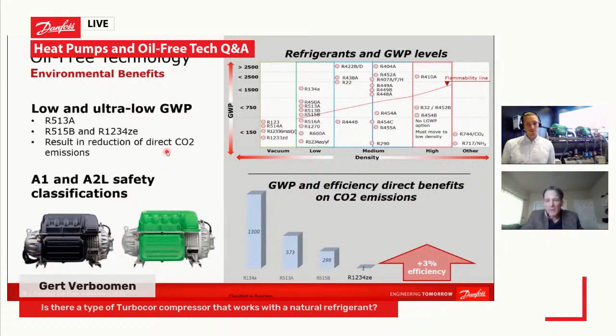One of the main related factors to this technology, as well as other turbo compressor technology becoming more prevalent in the market, is refrigerants and the push down to lower GWP levels. If you're going to push down to lower GWP levels and at the same time minimize flammability, that pushes you to lower density refrigerants. Lower density, or larger molecule, refrigerants in turn push you toward technology optimized to remove a high volume of that large molecule refrigerant - that's turbo technology, or dynamic compression in general. So we see the market moving more in this direction.